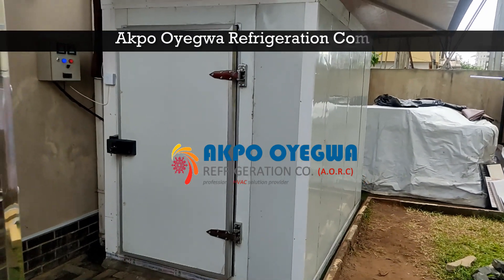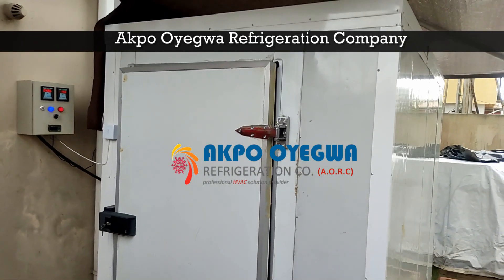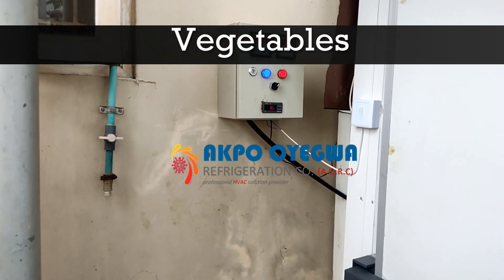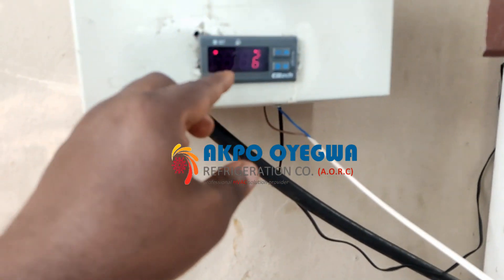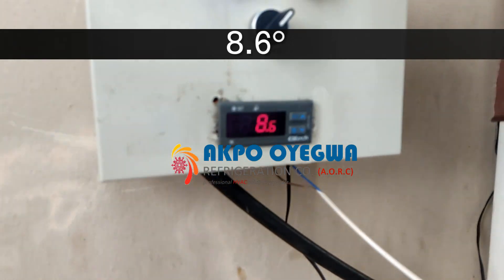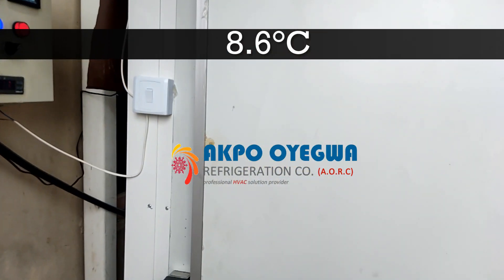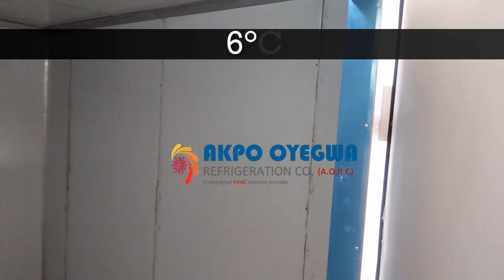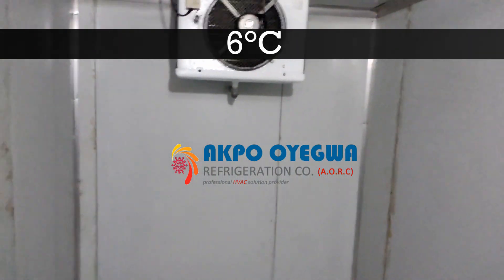This cold room was built in Lekki Phase One, Lagos State, Nigeria. As I've said, this cold room is built to store vegetables — the customer requested a cold room to store vegetables. The temperature at the moment is 8.6 degrees Celsius and we are approaching a temperature of 6 degrees Celsius. I'll be going in to see how well the cold room is running.